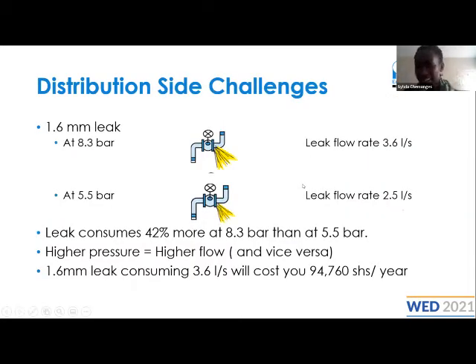So the flow rate of the leak at 5.5 bar is lower than it would be at 8.3 bar. So instead of cranking up the pressure, it would be ideal to just fix the leak. You will lose 40% more by increasing the pressure.